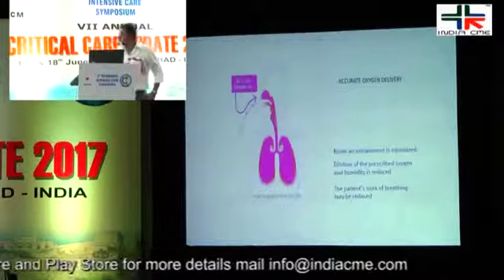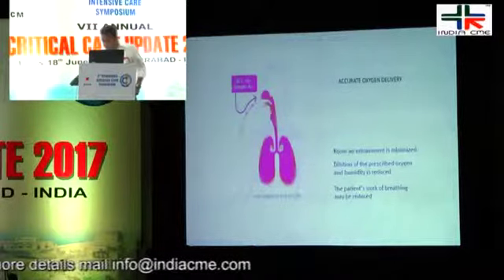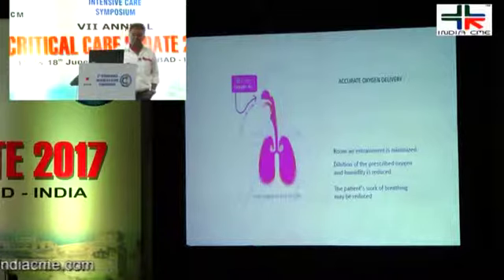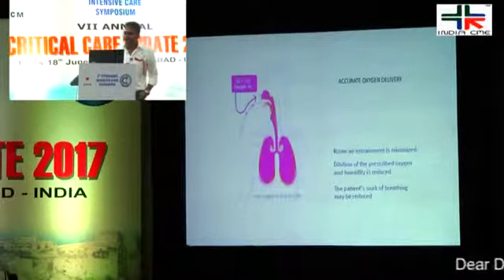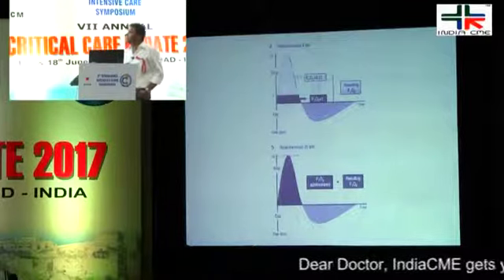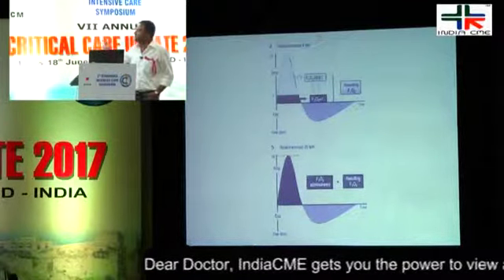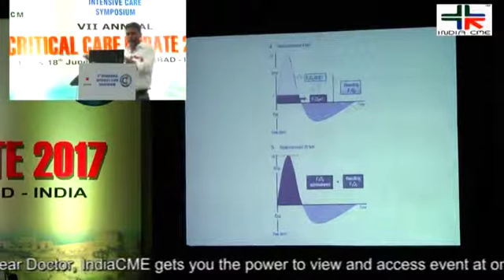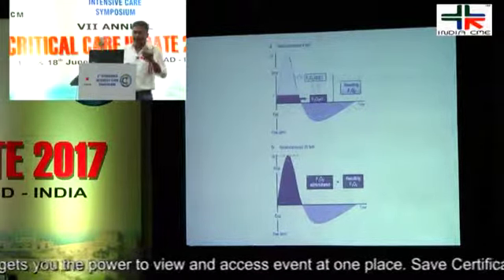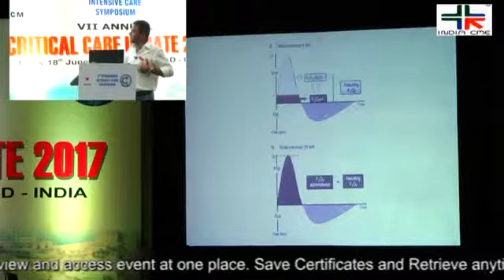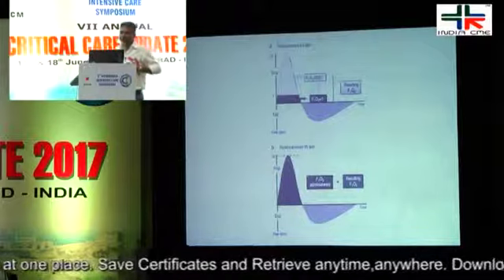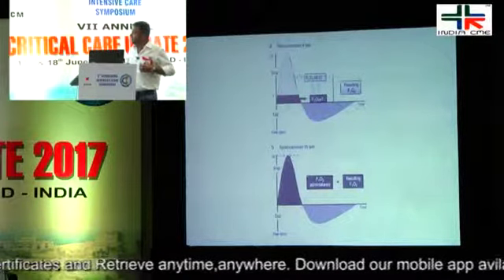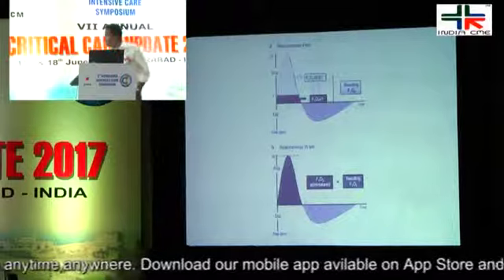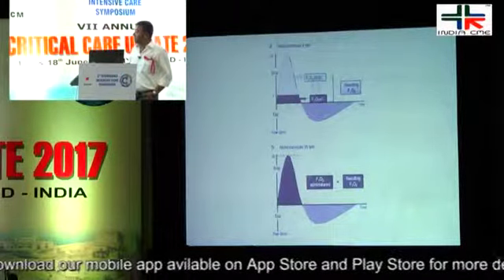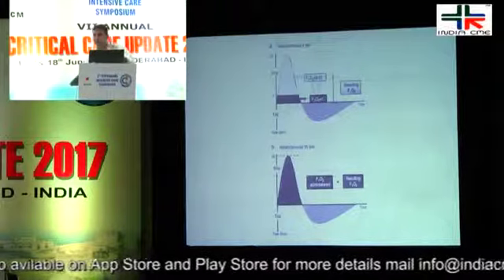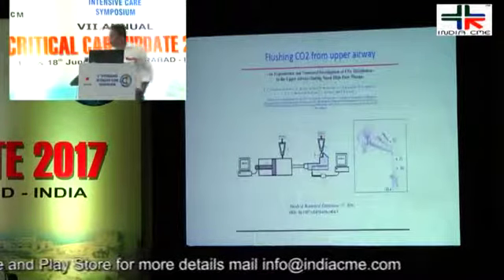But if your flow is much higher than the patient's inspiratory flow demand, there won't be any air dilution. So this exactly happens in nasal cannula. 4 liter, maybe the patient's demand is around 10 to 12 liters. So the rest of the 8 liters is coming from environmental air, and there is air dilution, and your resulting FiO2 is much less than what you are actually trying to achieve. But in standard HFNO, with more than 35 or 40 or even 60 FiO2 administered, that is actually the resulting FiO2 the patient is getting. That means that predictable and high FiO2 you can deliver.